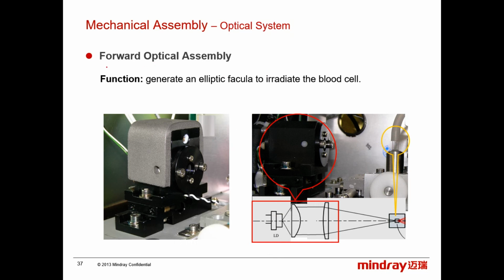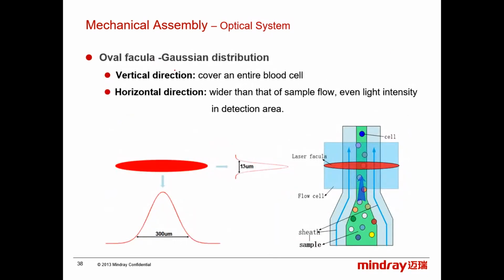So for the forward optical assembly, to summarize, it generates an elliptic facula to irradiate the blood cell in the flow cell. Here the diameter is 13 micrometer. Why do I need this? To make sure my cell will be hit entirely by the laser. This is the laser facula. As you see, it will be more than sufficient to hit the cell. For the vertical direction, it covers the entire blood cell. For the horizontal direction, it is wider than the sample flow, with even light intensity in the detection area.